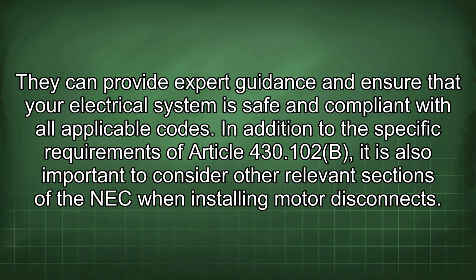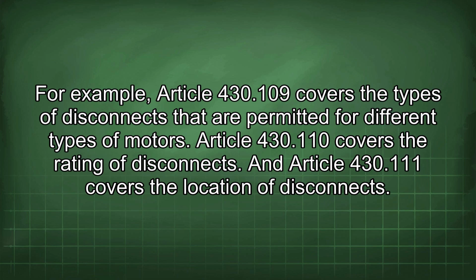In addition to the specific requirements of Article 430.102(b), it is also important to consider other relevant sections of the NEC when installing motor disconnects. For example, Article 430.109 covers the types of disconnects that are permitted for different types of motors.